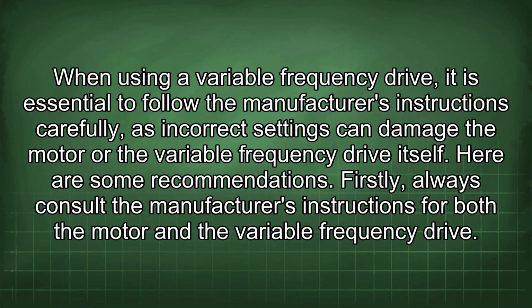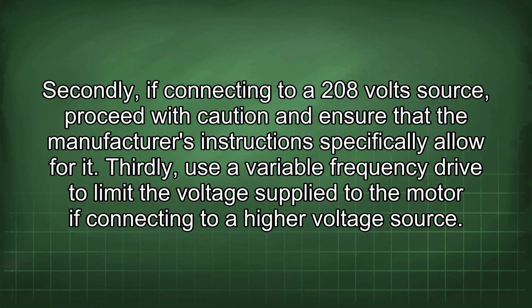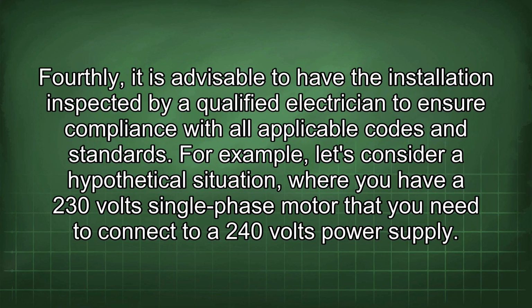Here are some recommendations. Firstly, always consult the manufacturer's instructions for both the motor and the variable frequency drive. Secondly, if connecting to a 208 volt source, proceed with caution and ensure that the manufacturer's instructions specifically allow for it. Thirdly, use a variable frequency drive to limit the voltage supplied to the motor if connecting to a higher voltage source.